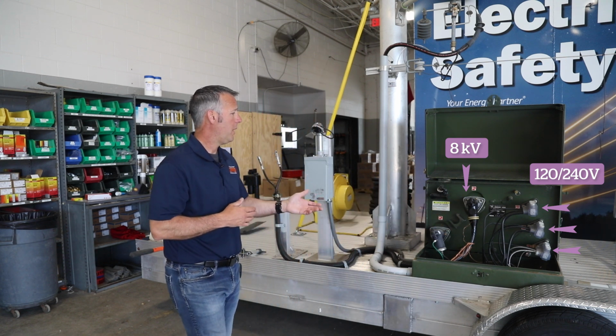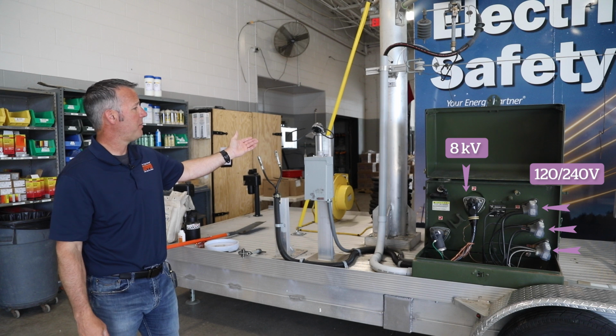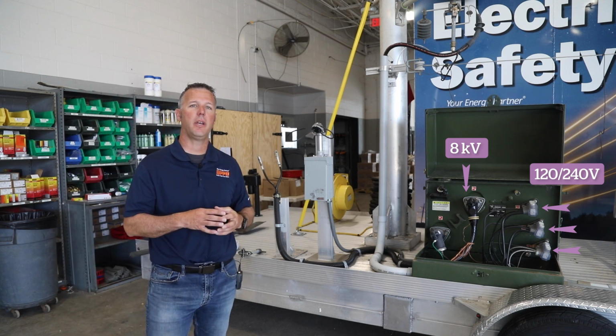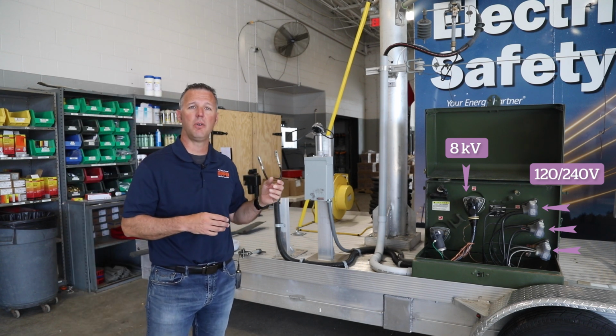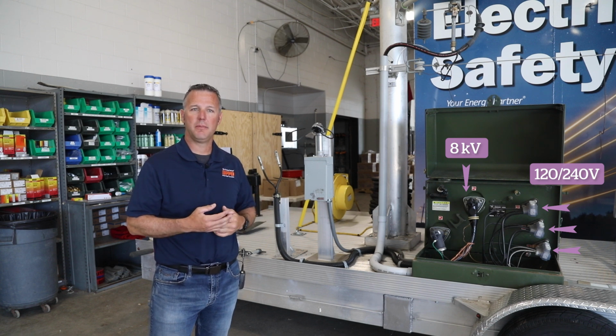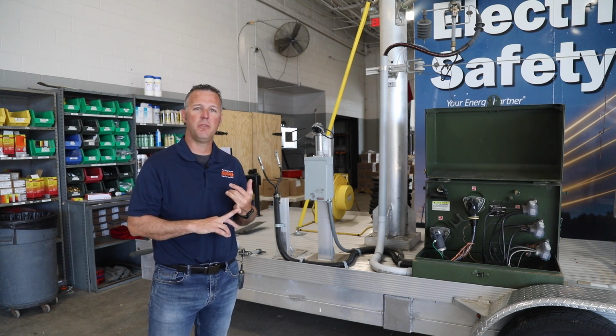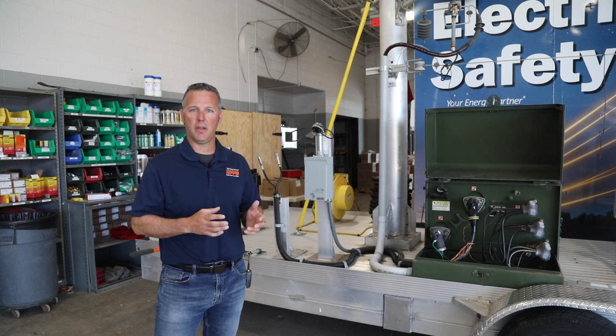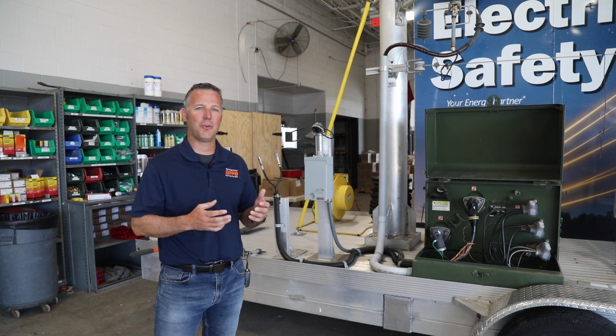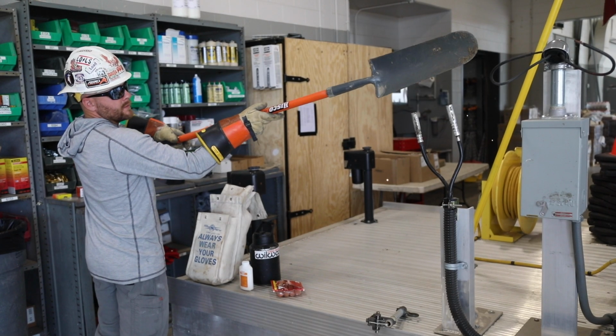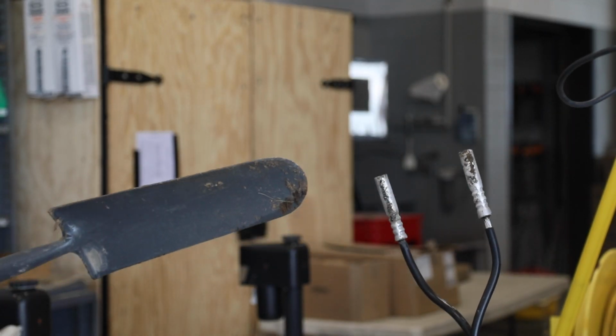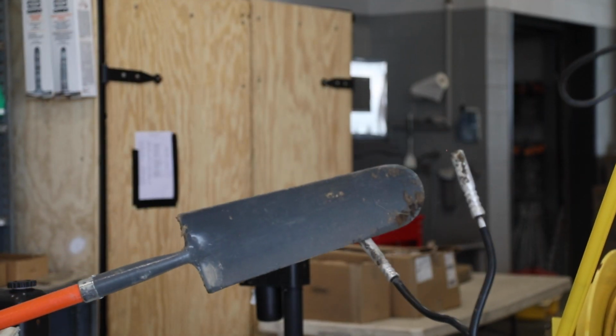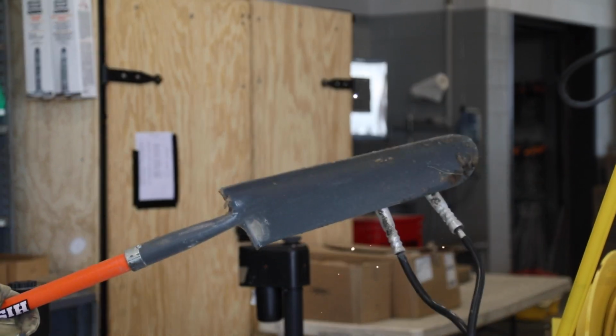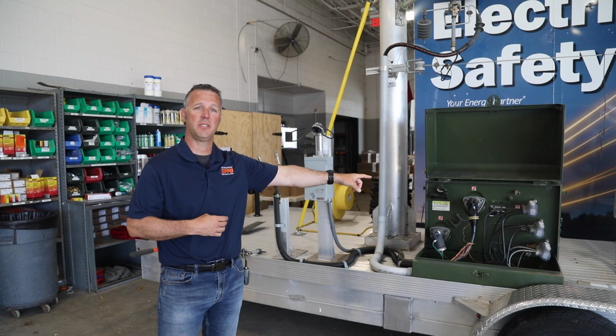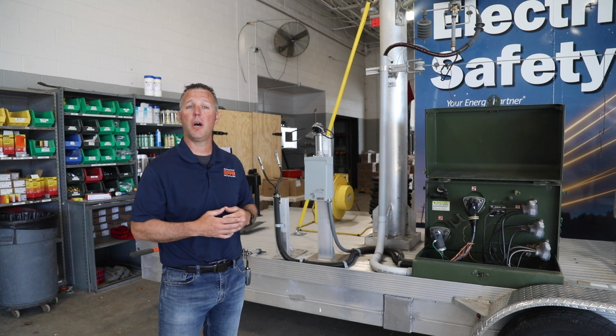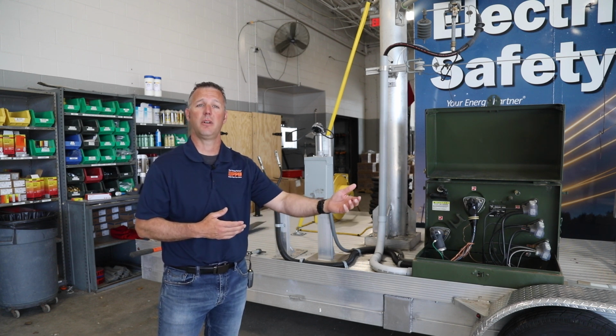Basically why we go through this is something that you'll see, but it's underneath the ground. It's coated and safe, but if you happen to hit it with a shovel, that's when problems start to happen. You can get into the 120/240, which a lot of times doesn't sound like as high as voltage, but it has a lot of amperage. So when you go to grab, let's say a secondary that's in a hole you've dug, it's not gonna let you go. It's gonna hold on to you until either it kicks out this transformer that's fused, or it just continues to pump because it sees it as a light switch that was turned on in your house.